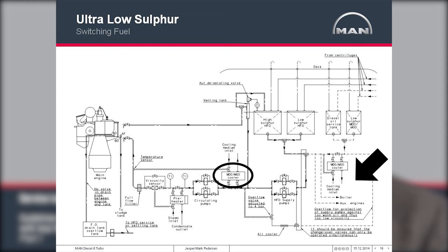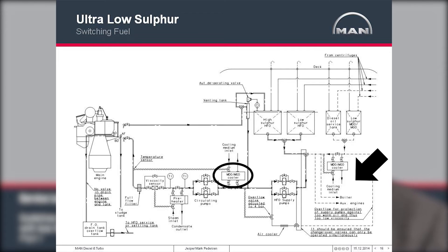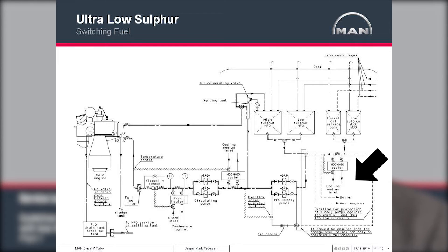Fuel coolers may also be needed for other appliances in the engine room itself. This could be for the supply pumps, the transport pumps, or even the boilers, which also have a requirement for 2 centi-stokes inside the pumps to avoid seizures.